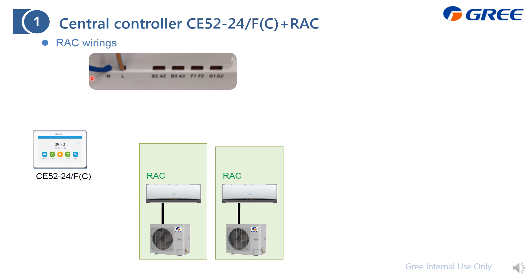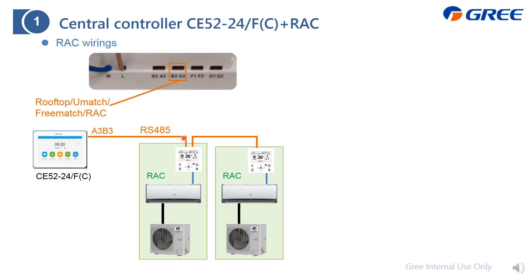Here is the wiring interface of the CE52. This LN is the power supply for the CE52. For the residential air conditioner, to control it we just need an adapter, which is the wire controller. The output is already RS485 with Modbus protocol, so we can combine them together and connect to this central controller.